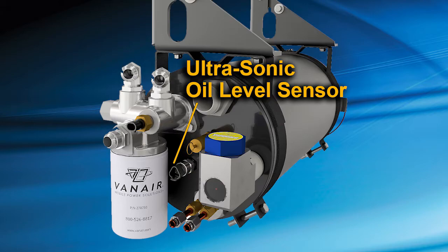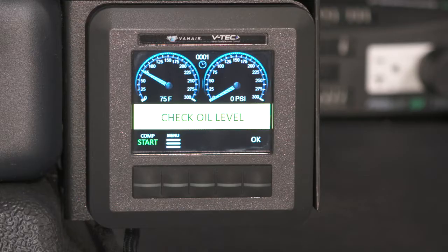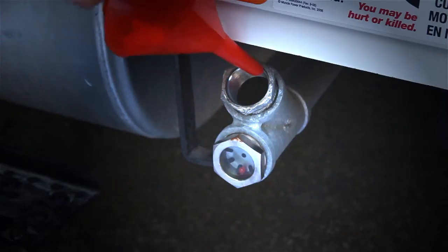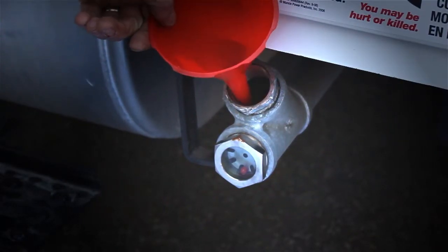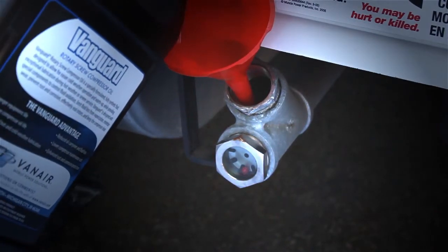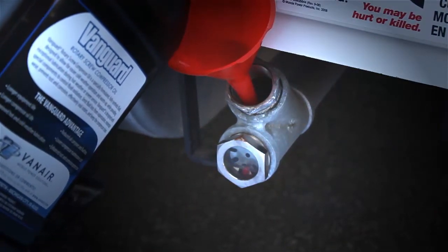Your ultrasonic oil sensor may display a check oil level. Should this occur, it is recommended to check your sight glass and add the appropriate Vanguard compressor oil in small amounts. Stop when the fluid level reaches the middle of the sight glass.